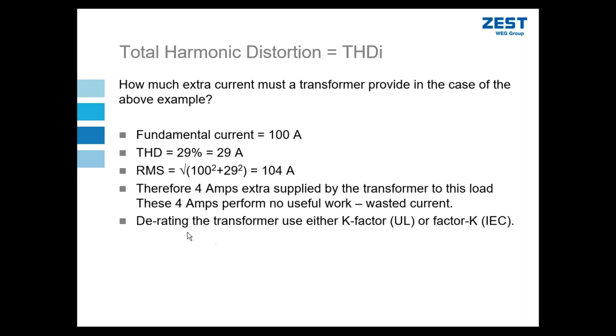So there are some ways that we derate and design transformers. Underwriters Laboratories from the US has a K-factor method, and IEC has a slightly different method. They call it factor K. Those we're not going to go into too much detail, but they have slightly different ways of how they specify how a user needs to deal with the transformer in the case of harmonics on the network.